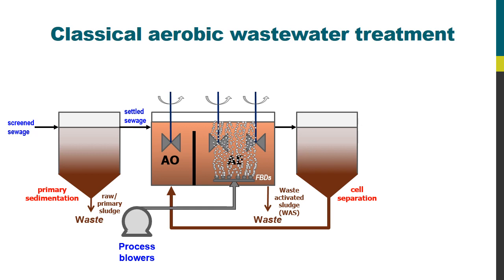So in effect, regular classical aerobic wastewater treatment is a two-stage process: the primary treatment, which is just a sedimentation process, and the secondary treatment, which is the biological tank followed by the cell separation stage, referred to collectively as the activated sludge process. Most wastewater treatment plants just comprise those two processes, maybe with a few added whistles and bells here and there.